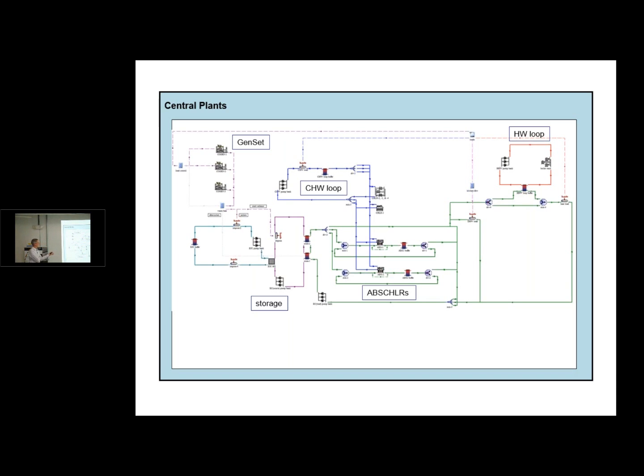This design evolved enormously over the course of the project. It's a bit of a funny situation, because when I was brought into the project, they were at something like 75% design development. They had blueprints, drawings, everything. The only thing they didn't have was the sequence of controls written down for the entire system. By the time we did our lab on this, which is what you're looking at, probably 8 months later, the last design I got was literally a scan of a napkin with a sketch on it. And that, of course, then got developed once more.